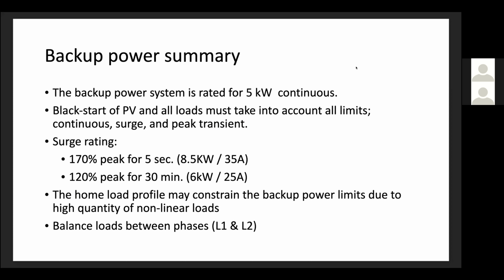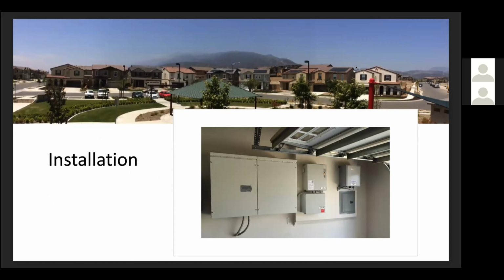Again, the surge rating is 170% of nameplate peak for 5 seconds or 120% peak for 30 minutes. The home load profile may constrain the backup power limits due to a high quantity of nonlinear loads. And you've got to make sure that you balance your loads on that backup loads panel between the phases, both L1 and L2. All right, that's all the boring, important stuff.